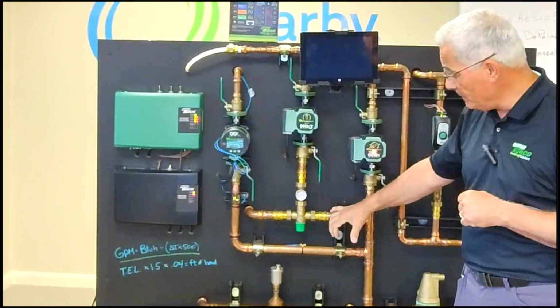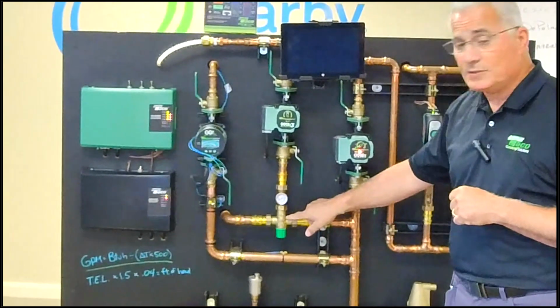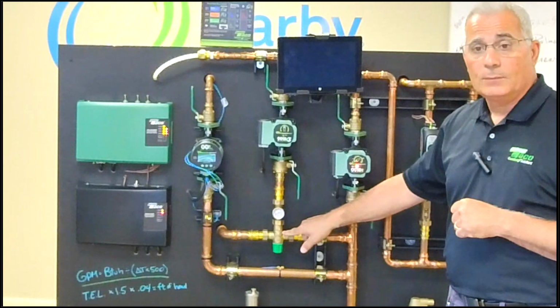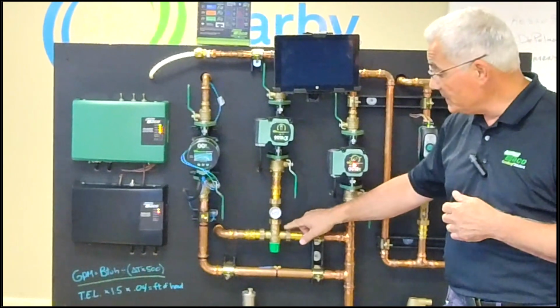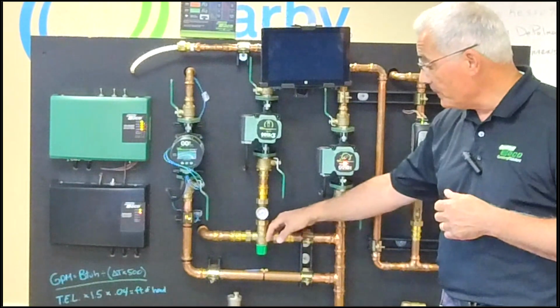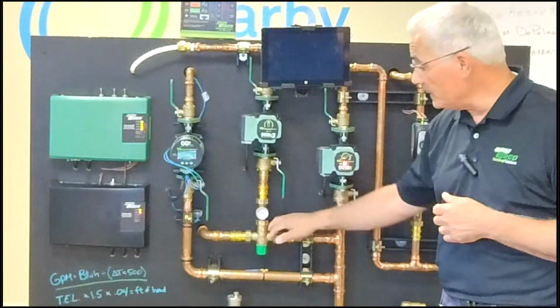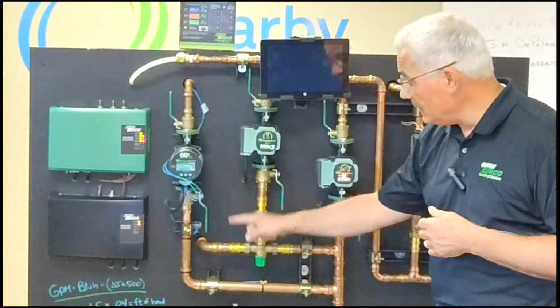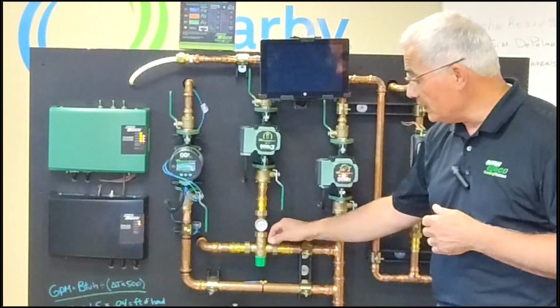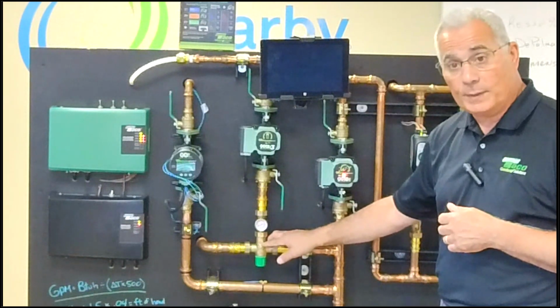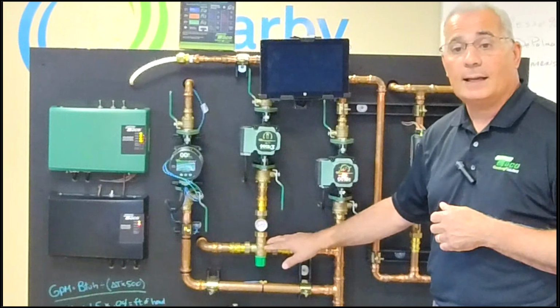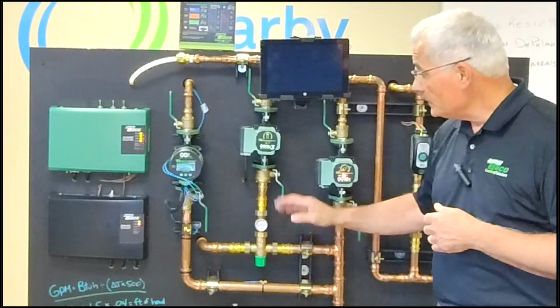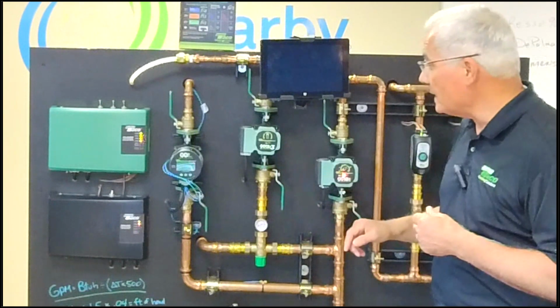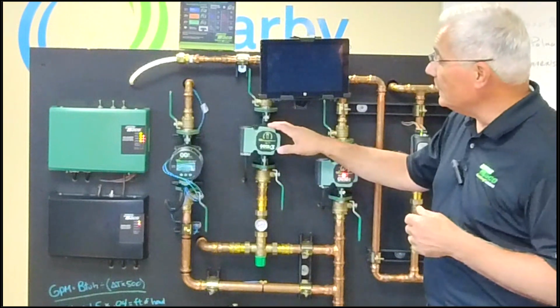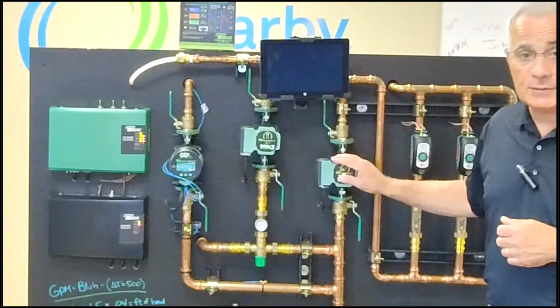We would never have the pump here because that will force this open when I don't need it open, because when I sense enough temperature at the mix valve, it will close off this port and I'll only be circulating here. If I need more temperature, it'll slowly open up this port to let some of that higher temperature in. So that circulator always goes on the mix side out. So this circulator has to be independent from this circulator.